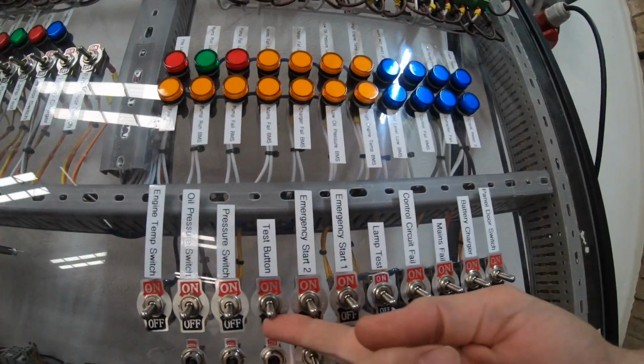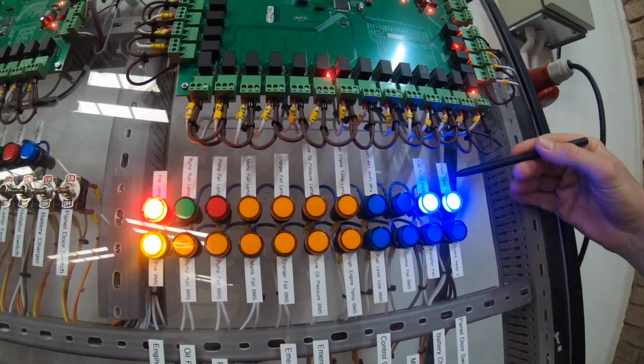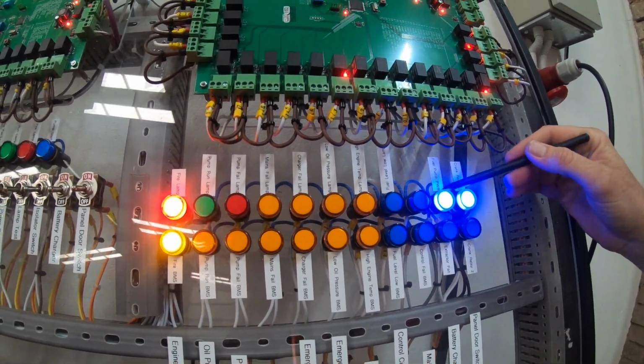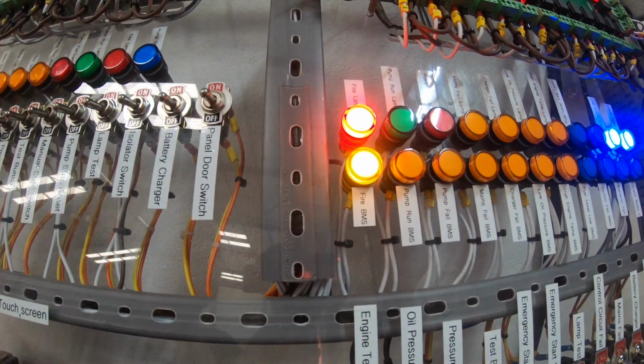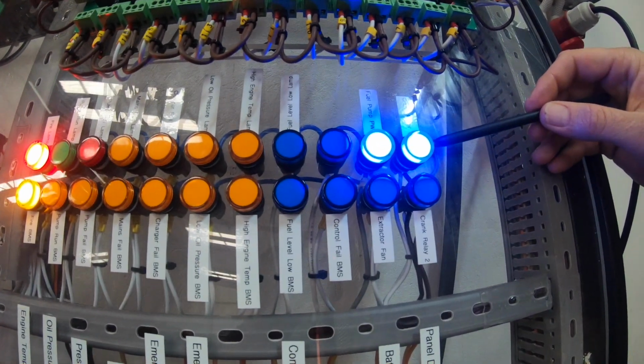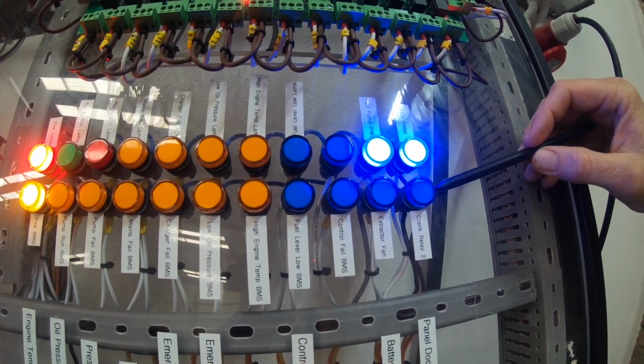We're now going to use the test button. Crank relay 1 started. Pump power. Fire lamp LED. Just go back to here, we go watch the crank. After the 15 seconds, it'll switch over to crank 2.